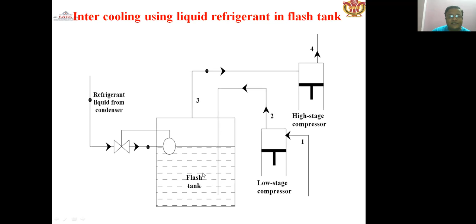Intercooling using the liquid refrigerant in the flash tank may or may not reduce the power input to the system, as it depends upon the nature of the refrigerant. The heat rejected by the refrigerant during intercooling generates additional vapors in the flash tank, which have to be compressed by the high stage compressor. Thus, the mass flow rate of the refrigerant through the high stage compressor will be more than that of the low stage compressor.